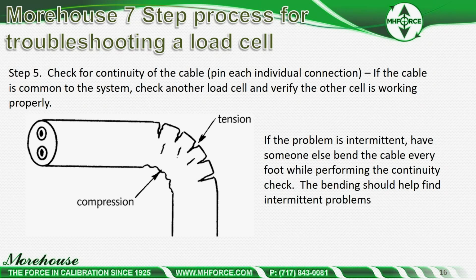So this happens quite a bit to us. The cell appears to be working. We rotate the load cell. When you rotate it, you reposition the cable, and then all of a sudden the load cell doesn't work. The majority of the time the problem is an intermittent cable, and this can be very difficult to diagnose. So that's why you get somebody else, keep bending the cable and check for the intermittent signal.